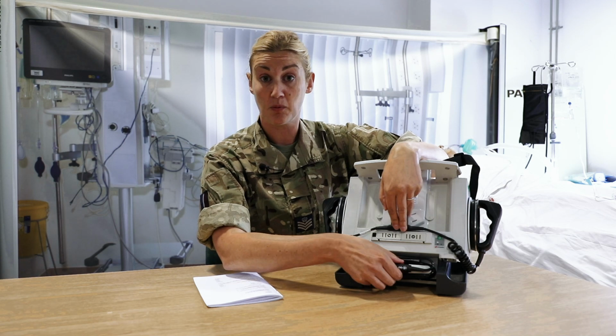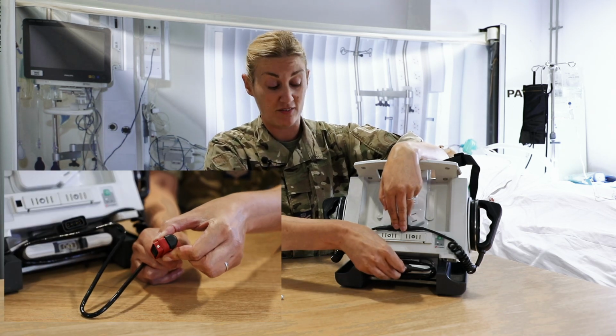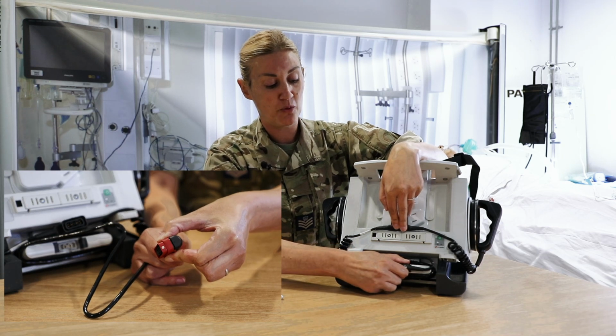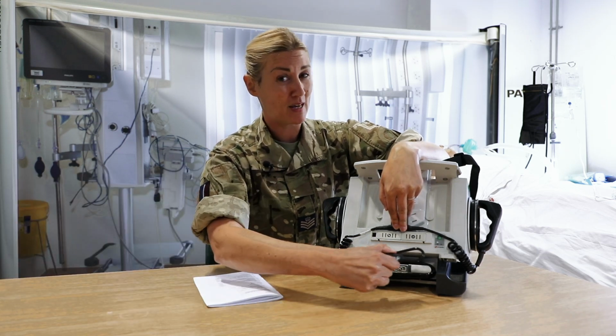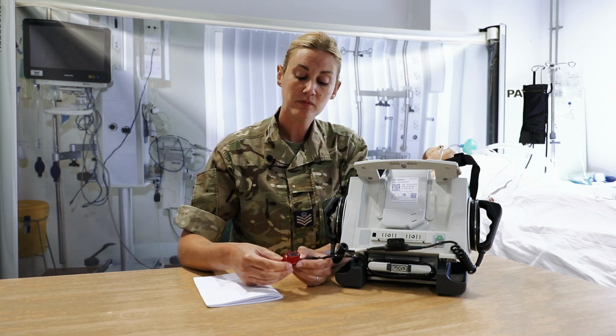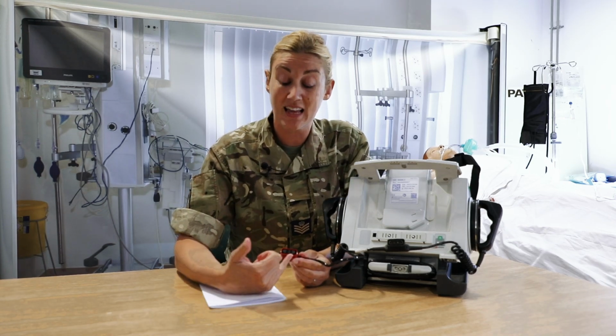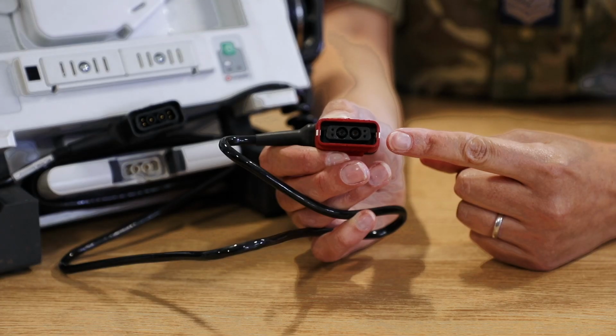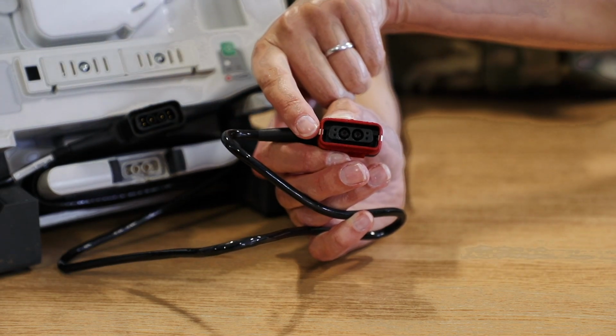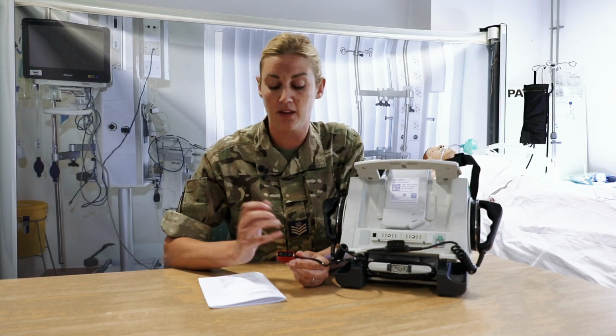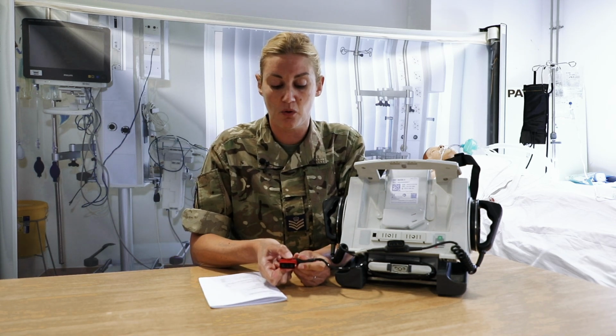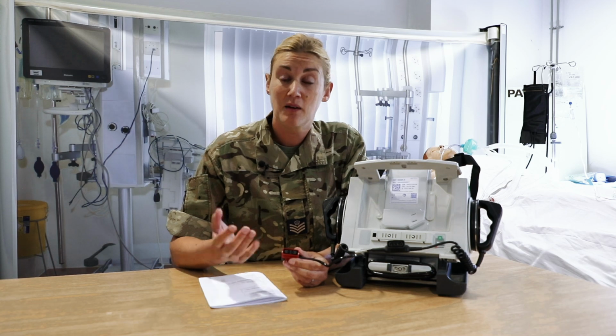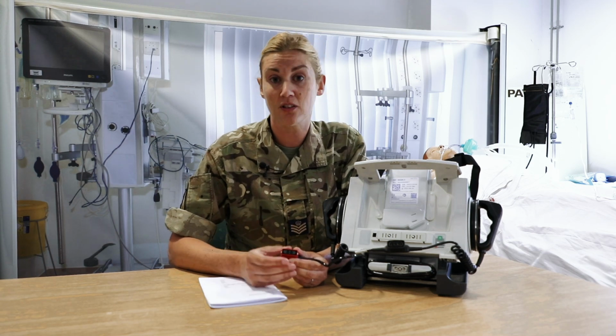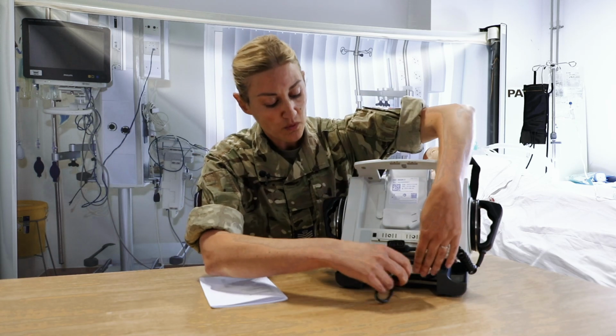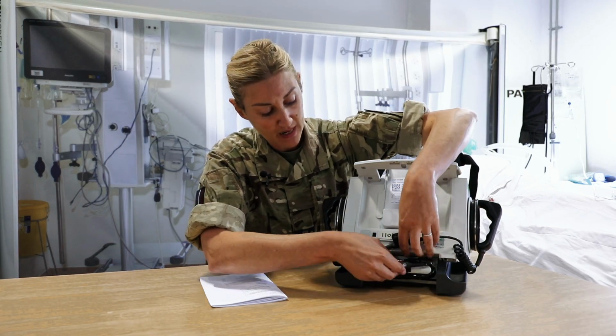To remove the red master cable, we're going to pinch the two red parts of this sort of housing jacket, and then we pull them backwards, and the red master cable can be a bit stiff, but it should just come out. And once it's out, we're going to make sure that there isn't any dirt crusted up in there preventing it from working. And really importantly are these two little white clips, which can be quite delicate and will break if people just pull the red master cable out without any thought to this jacket that holds it in place. Make sure that they're intact, because if they are loose or broken, then the connection to the patches may fail. Once you're happy with the master cable, then just replace it back into its housing.